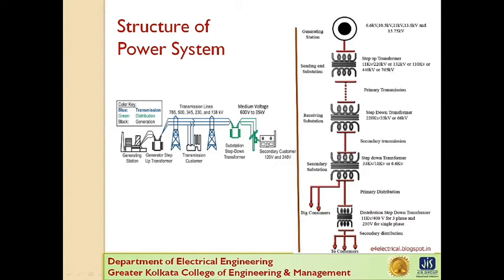Next, primary transmission. The electric power at 132 kV is transmitted by a three-phase three-wire overhead system to the outskirts of the city. This forms the primary transmission, where the power is transmitted at 132 kV by a three-phase three-wire system. Now, secondary transmission. The primary transmission line terminates at the receiving substation, which usually lies in the outskirts of the cities.